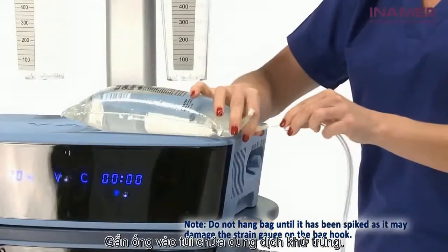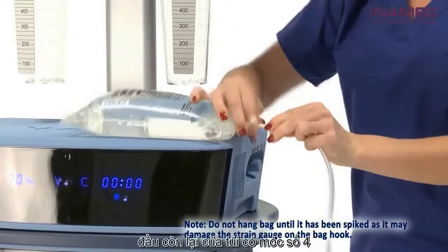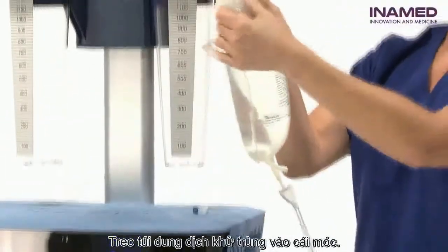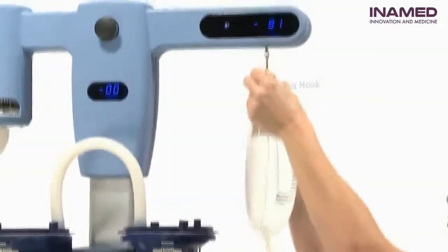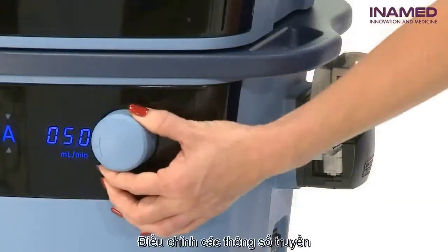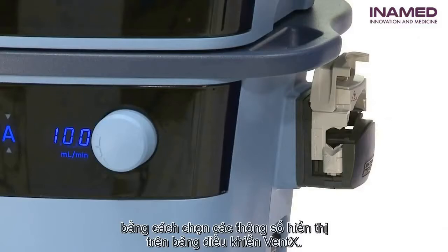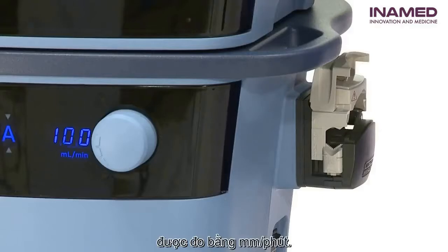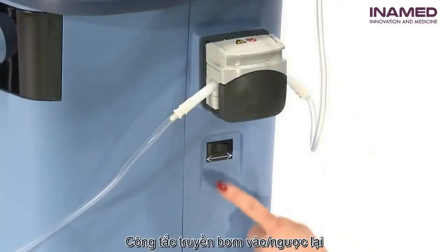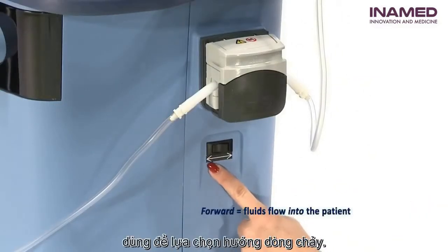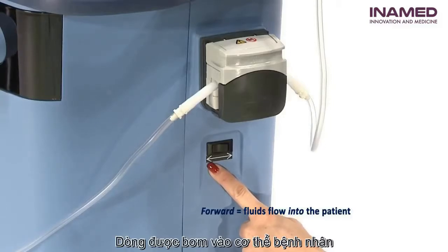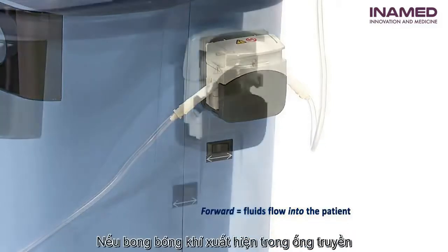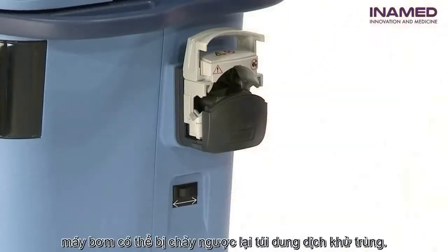Insert the bag spike into the sterile fluid bag. Without pulling on the IV bag hook, hang the sterile fluid bag on the bag hook. Using the infiltration rate control, select the flow rate indicated on the VentX front display panel. The infiltration flow rate is measured in milliliters per minute. Using the infiltration forward-reverse switch, select the flow direction. Fluid should be pumped toward the patient, indicated by the forward switch. If air bubbles are present in the infiltration tubing, the pump may be reversed to direct the flow back into the sterile fluid bag.